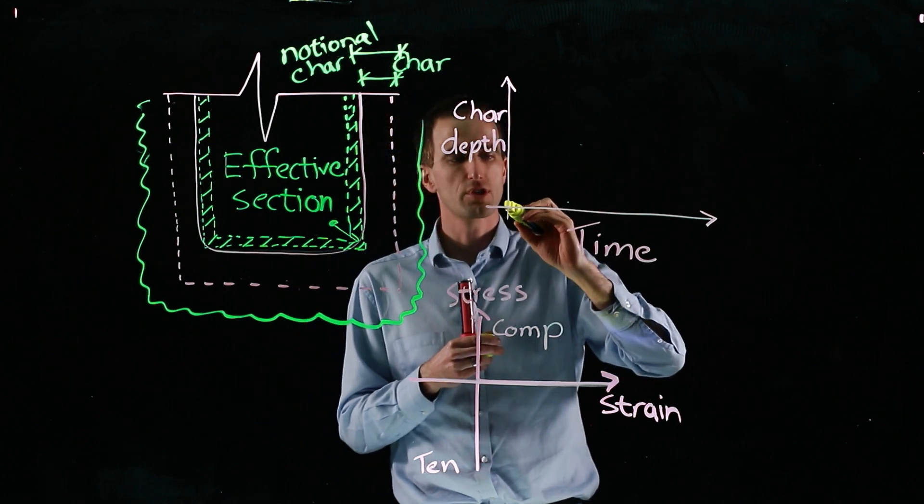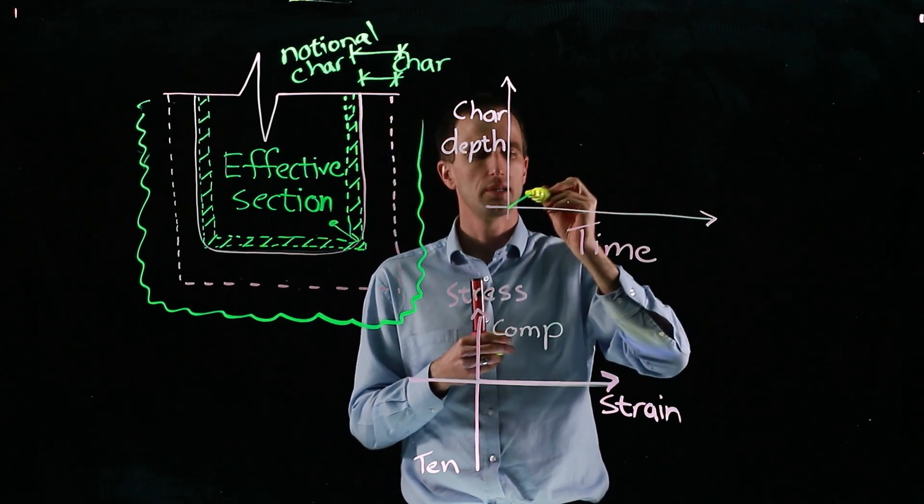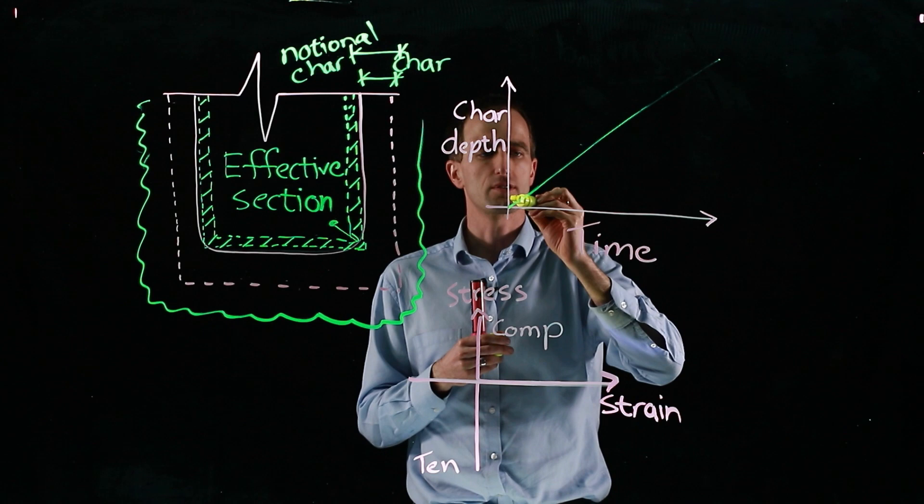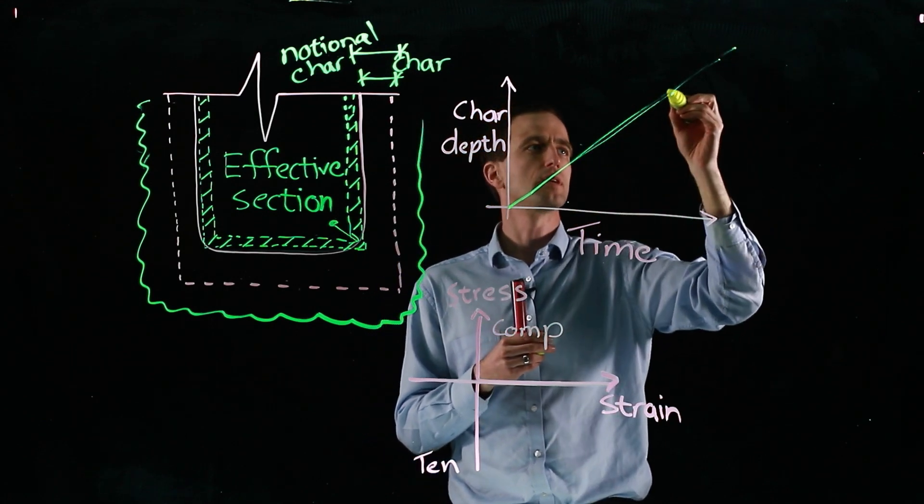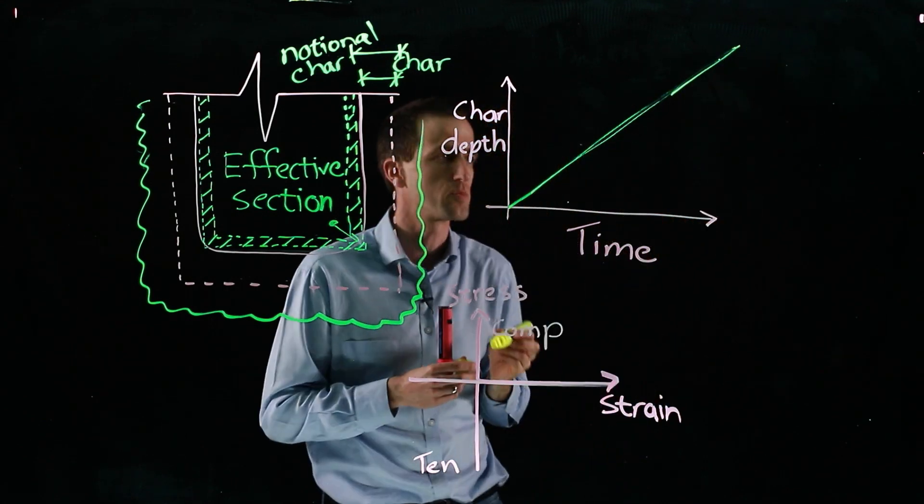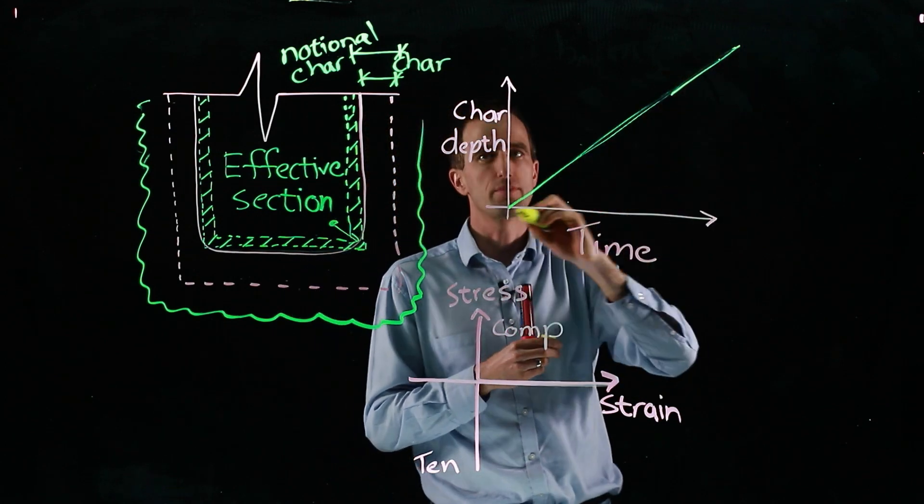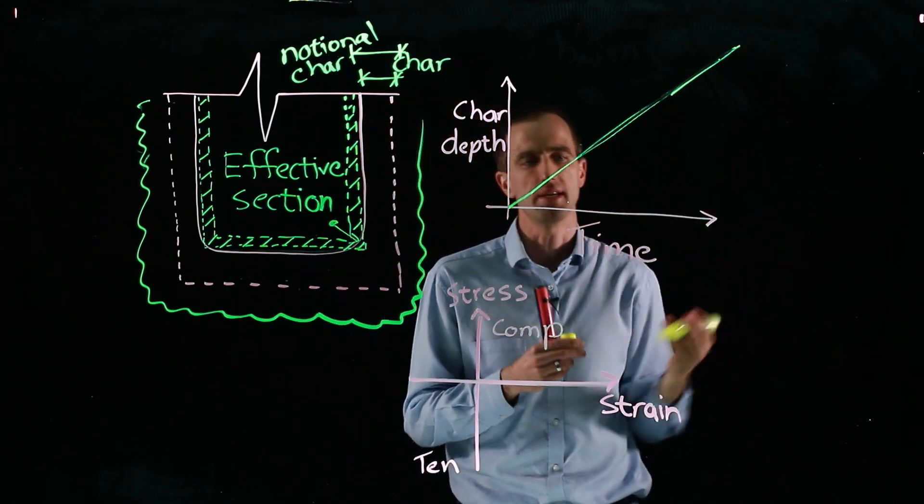And if I just have straightforward charring unprotected timber, it'll look something like that approximately. It's just a straight line depending on which model you use. As time progresses, the char depth linearly increases.